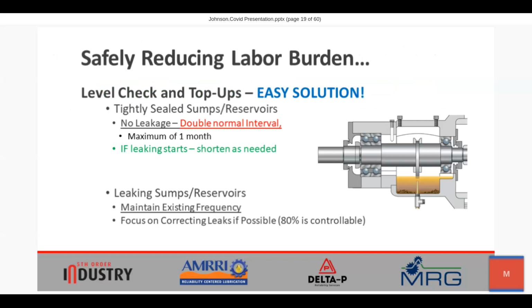This is an easy solution where we have tightly sealed sumps and reservoirs where there is no leakage. We should look to double the normal service intervals for the care and feeding of our machines. I would propose that we not go beyond a month because a lot of things can happen within 1 month. But if we're currently experiencing daily to weekly service intervals, we can safely extend those as long as the machine is not leaking. And of course, once we identify any instance of leakage, we should shorten that back to our starting point, or at least shorten as needed.